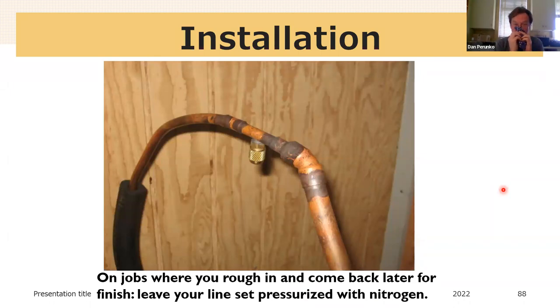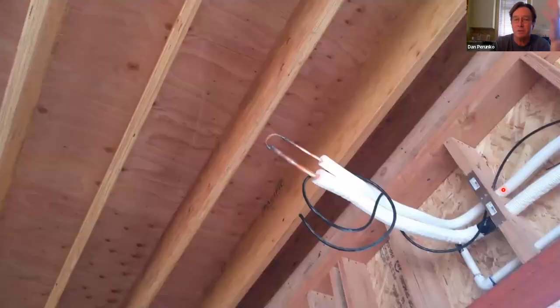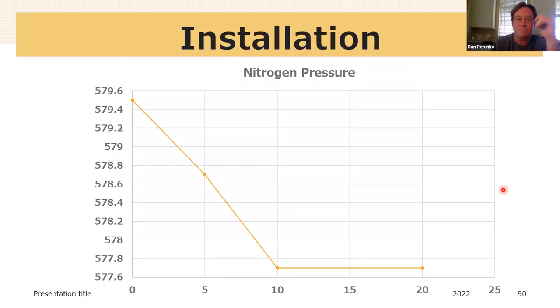On new construction jobs, we frequently have to put the line sets in and then come back later to finish the job. So we always build the line set, braze it closed, and pressurize it with nitrogen so that it's sitting in a clean, dry state. And then if someone punctures it, it blows off nitrogen and someone notifies us. So that's a system at rough install.